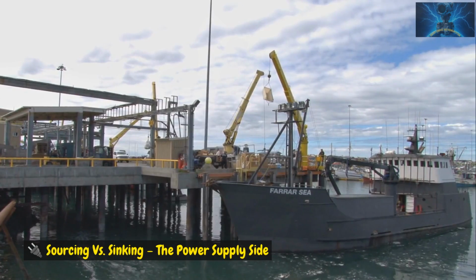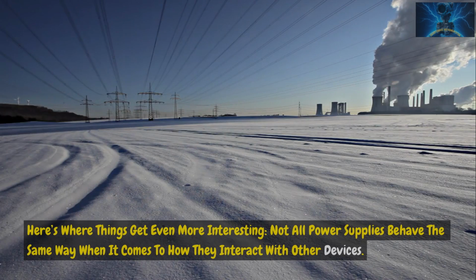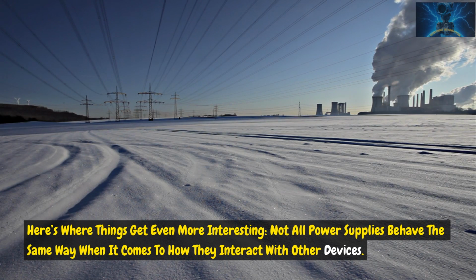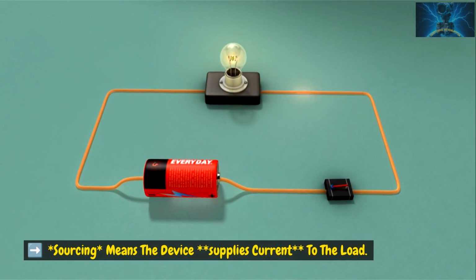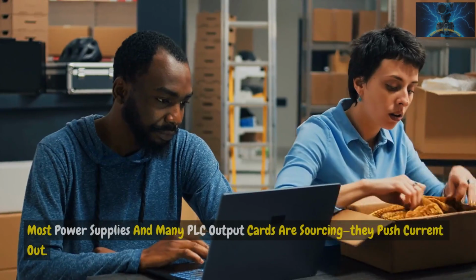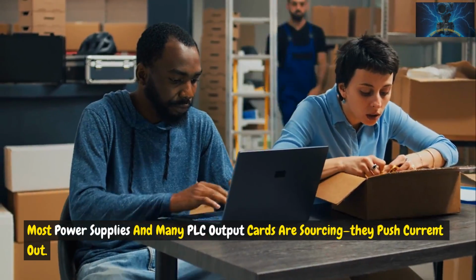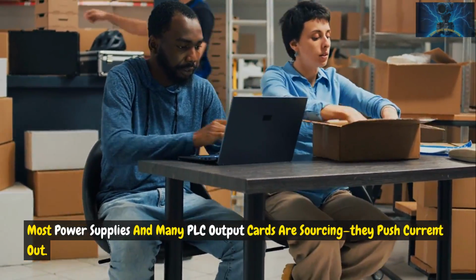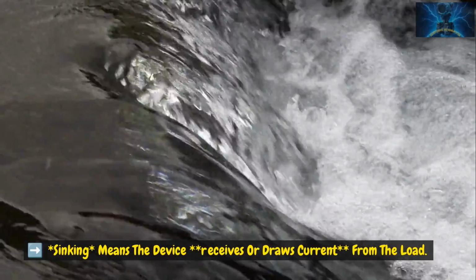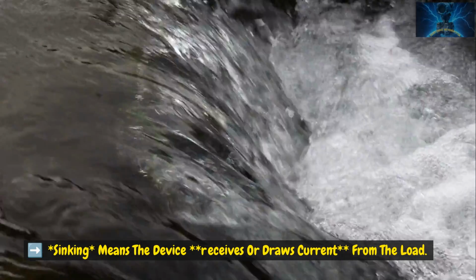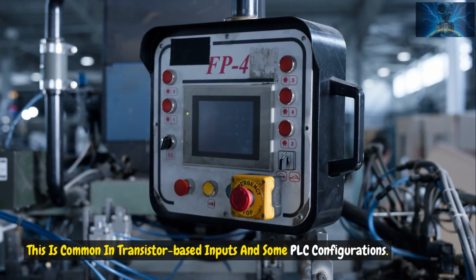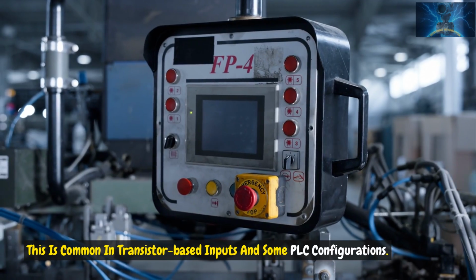Sourcing versus sinking, the power supply side. Here's where things get even more interesting. Not all power supplies behave the same way when it comes to how they interact with other devices. Sourcing means the device supplies current to the load. Most power supplies and many PLC output cards are sourcing. They push current out. Sinking means the device receives or draws current from the load. This is common in transistor-based inputs and some PLC configurations.